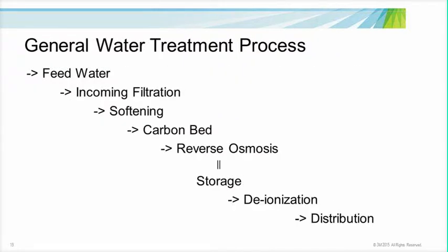In the following flow diagram, we see a depiction of a general reverse osmosis deionization water treatment system. We start with our incoming source or feed water, and to reiterate Emily's statement, the expectation is that incoming water will meet EPA regulations for drinking water. Our pretreatment stage includes a sediment filter to remove incoming suspended solids, followed by a water softener to remove hard minerals, which can cause scaling on equipment. The softener is followed by a carbon bed for removal of chlorine and reduction of organic impurities.